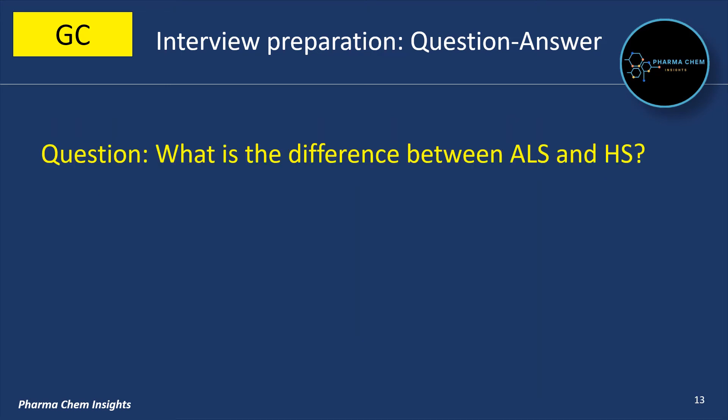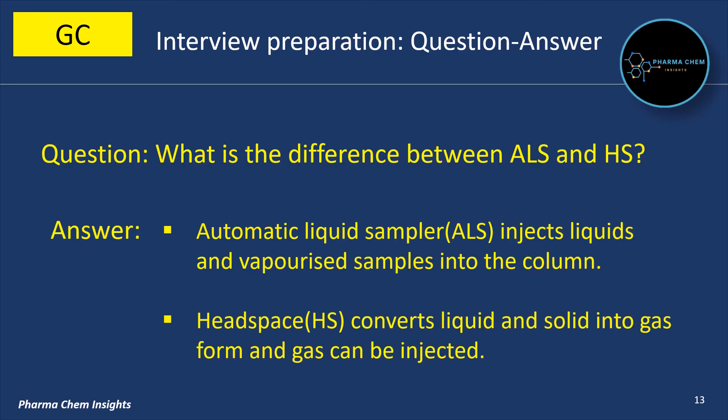Next question: What is the difference between ALS and HS? Automatic liquid sampler (ALS) injects liquids and vaporized samples into the column. Headspace (HS) converts liquid and solid into gas form, and the gas can then be injected.